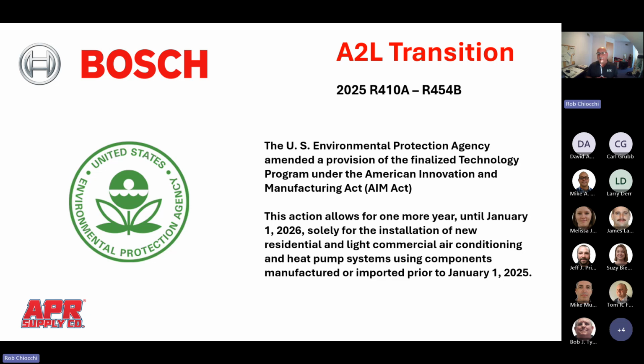The EPA amended the original AIM Act, now granting us a 1-year sell-through through 2025 of any remaining R410A product that may have been produced prior to January 1, but still in stock at the manufacturer or at the distributor. But come January 1, 2026, the AIM Act stipulates that nobody can sell or install a piece of equipment that utilizes a refrigerant above the threshold of 700 global warming potential. So simply that means we have a 1-year sell-through of the R410A product that still exists in the industry today.